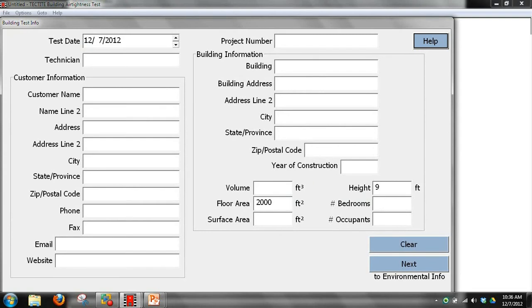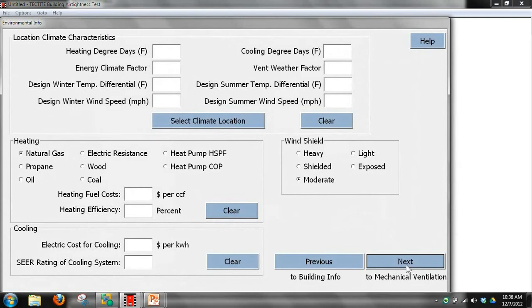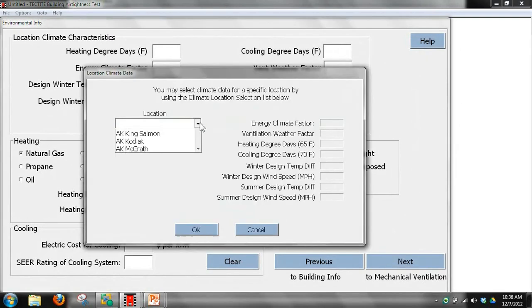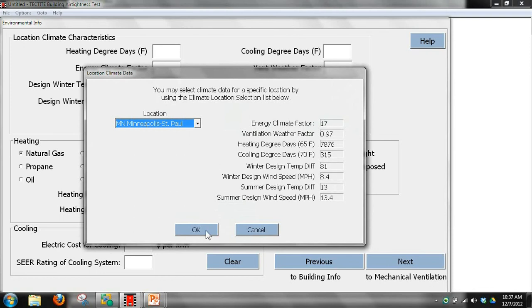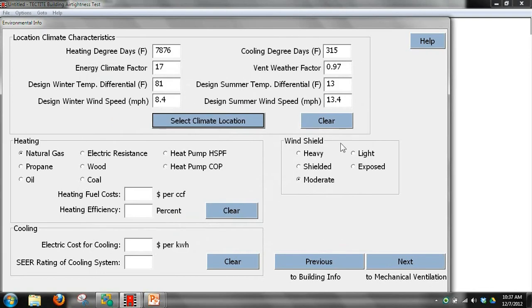If you don't enter number of bedrooms or occupants, it will assume one occupant. But if you enter three bedrooms, it's going to assume four occupants — the number of bedrooms plus one. We also need to enter our climate location so it can convert CFM 50 to CFM natural, and then enter our wind shielding. The help menu will give you guidance on deciding what the wind shielding is.